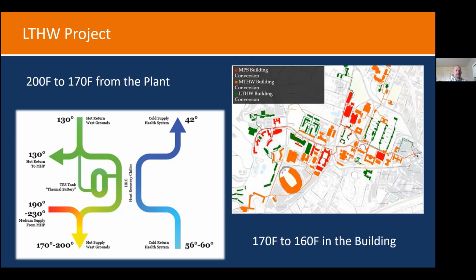We're in the middle of a project converting buildings, as illustrated in the image on the right showing all the buildings affected by this conversion. The main heat plant is here, feeding steam and medium temperature hot water all the way up to the most distal points of our system, including Gooch Dillard, Hereford, Kellogg, and way across at Carrs Hill and the International Residential College.